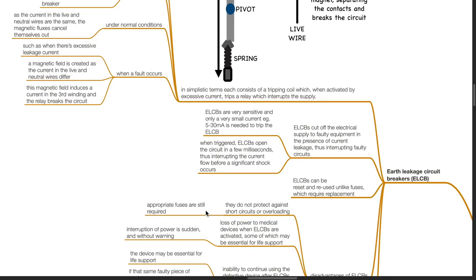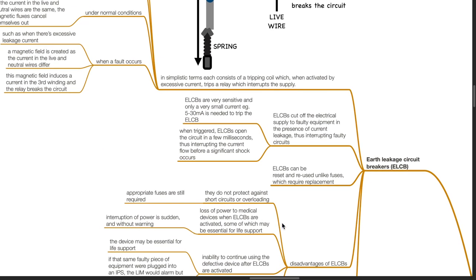ELCBs cut off the electrical supply to faulty equipment in the presence of current leakage, thus interrupting faulty circuits. ELCBs are very sensitive and only a very small current, 5 to 30 milliamps, is needed to trip the ELCB. When triggered, ELCBs open the circuit in a few milliseconds, thus interrupting the current flow before a significant shock occurs. ELCBs can be reset and reused unlike fuses which require replacement.